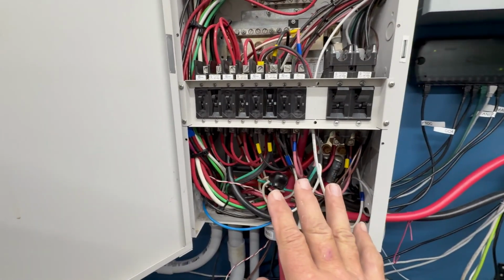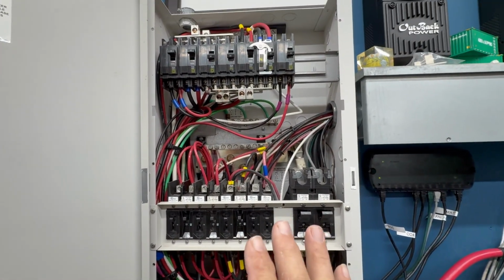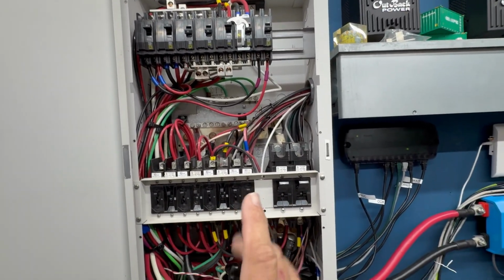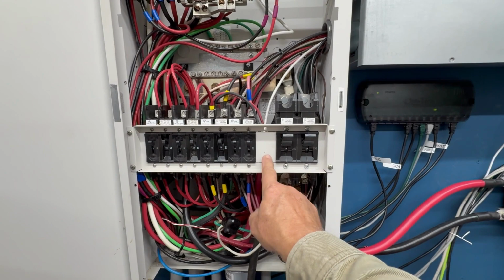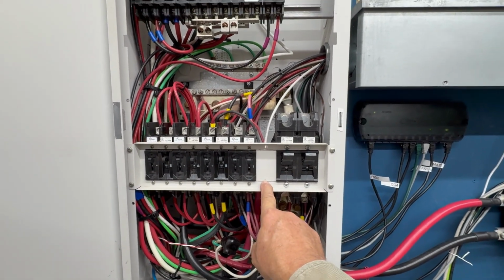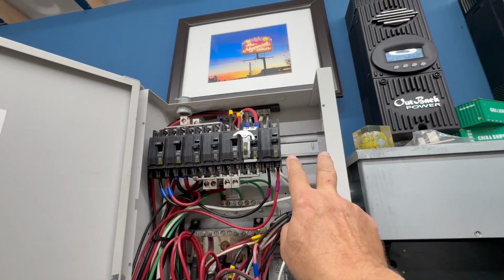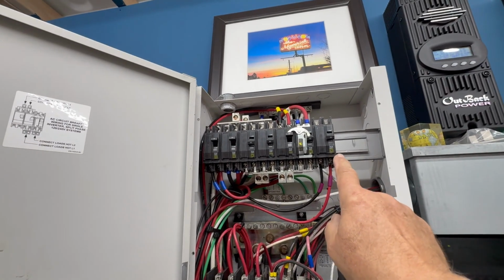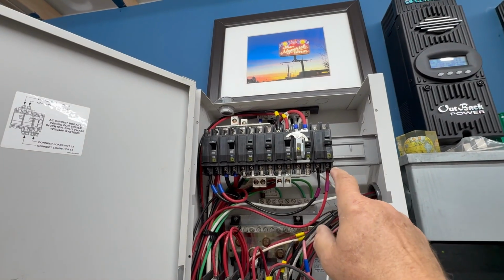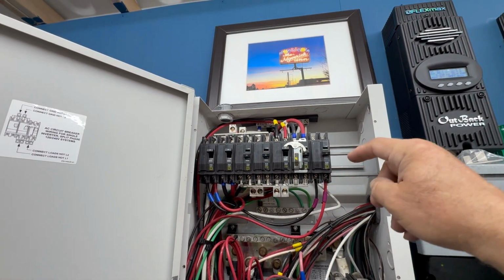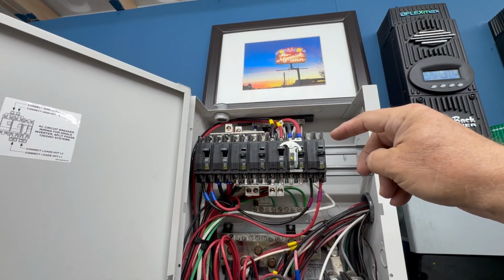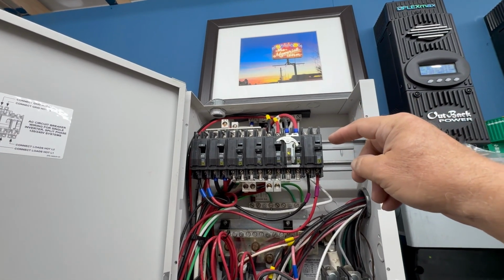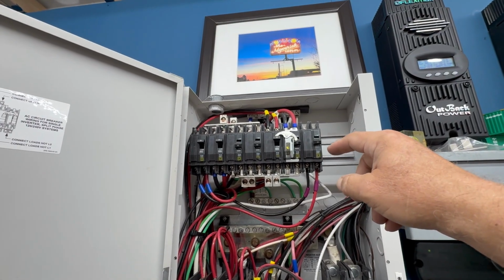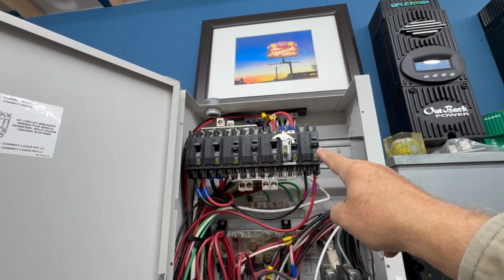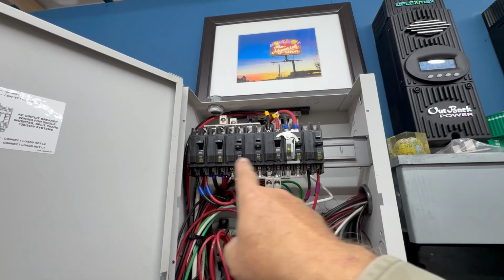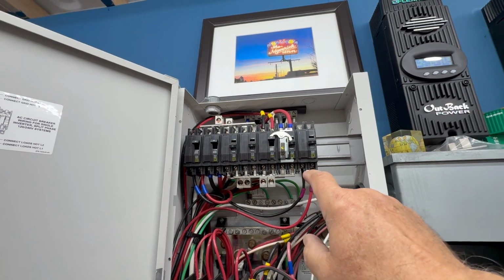It is full, okay? It is very full in here. It's not completely full because there's still a little bit of room. For instance, I can add another 250 amp DC breaker here, and I have 2 more spots for these nominally 60 amp feed through breakers. So I think with the Duo 21, I'll need 100 amp breakers here. So they are available. I will get 2 of them, one for the input and one for the output.